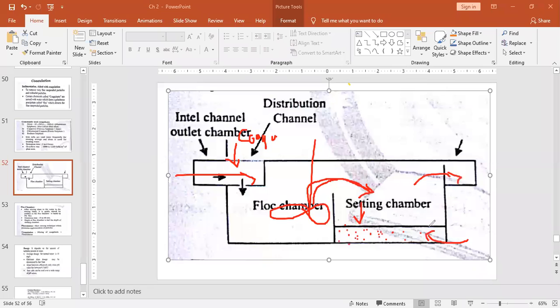This removal of sludge is not a regular process; randomly, once in a week or once in a fortnight, while the continuous settling process keeps going on, and the continuous clear water will be moved out. The inlet and outlet are arranged at the same height. So this is the sedimentation with coagulation process.